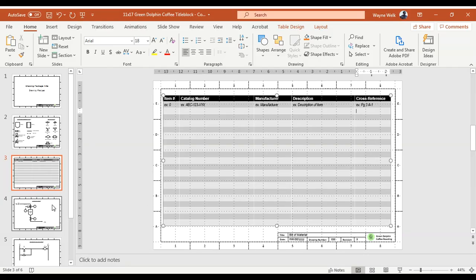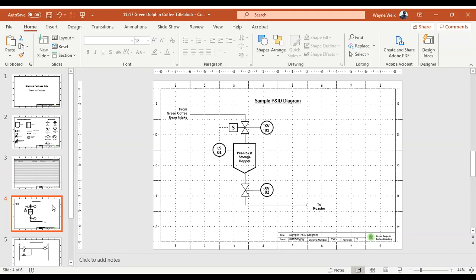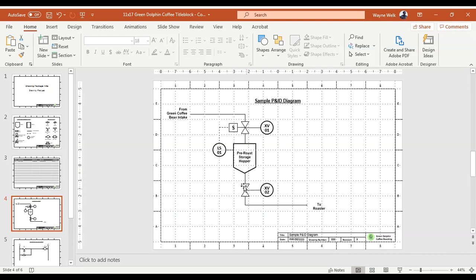The next page is a sample P&ID diagram. I've spotted you a good starting point. I've got a solid black line indicating piping — or in our case a conveyor — showing where the coffee beans are coming from. The process flows from the green coffee bean intake into the hopper and out to the roaster. We go through a solenoid valve with its own label and an electrical connection to the level switch tied to the pre-roast storage hopper, then another valve going out to the roaster.